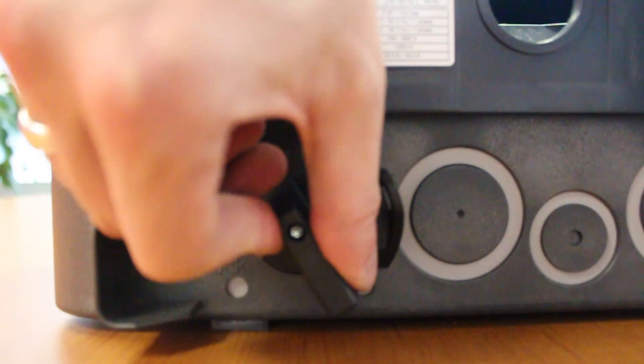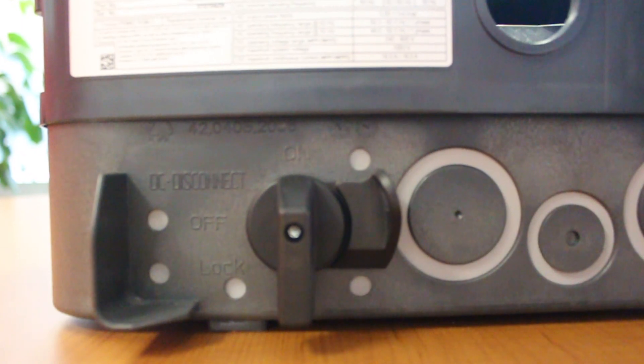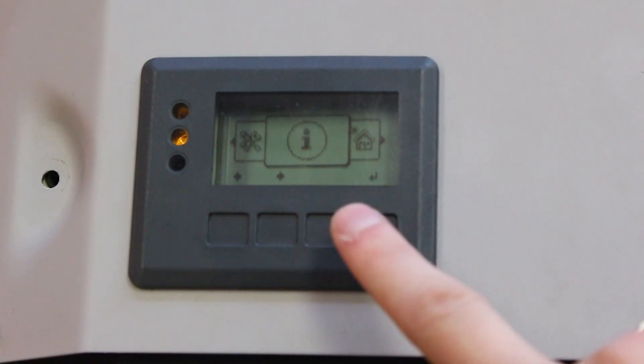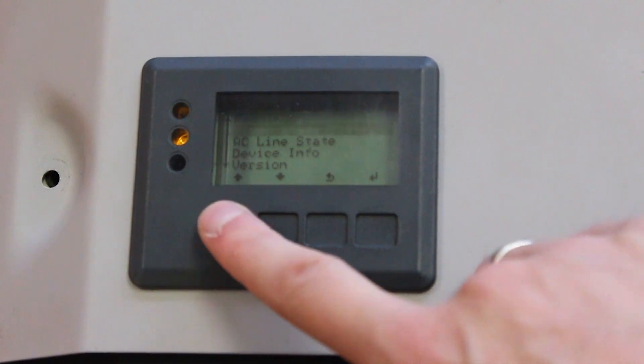Ensure that the DC switch of the inverter is on. Then navigate to the info menu, then go to readings within the info menu and within the readings menu look for PV ISO.